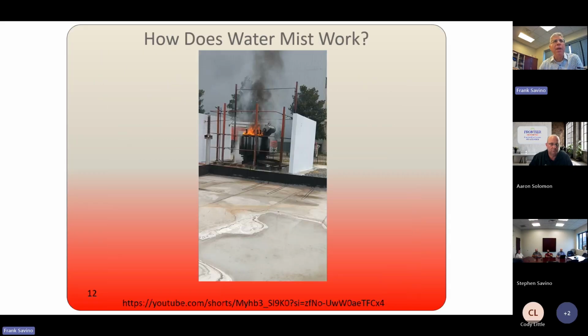So here's a water mist system protecting a transformer. So that was pretty impressive. You really see it's almost like a fogging effect. And the amount of water compared to, say, a water spray system is significantly less. And it did a really, really good job of surrounding the fire, surrounding the object, and extinguishing it.